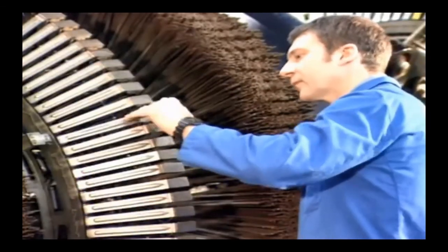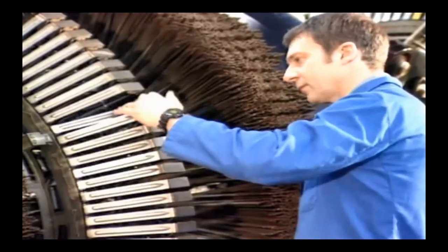This is a 56-inch diameter MFL tool, and they are checking that the sensors are moving correctly. So it's a mechanical check to confirm the mechanical integrity of each sensor prior to the run. So this one is in the workshop, and you can go there and audit that everything is tested in the way that guarantees that you will have a good inline inspection.